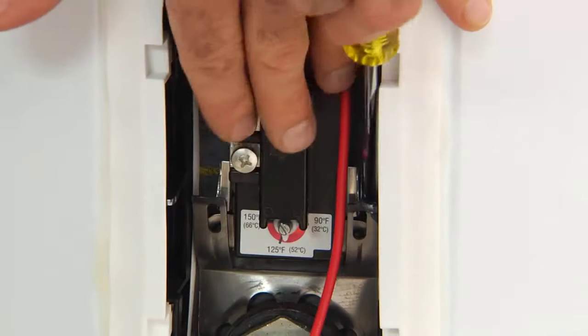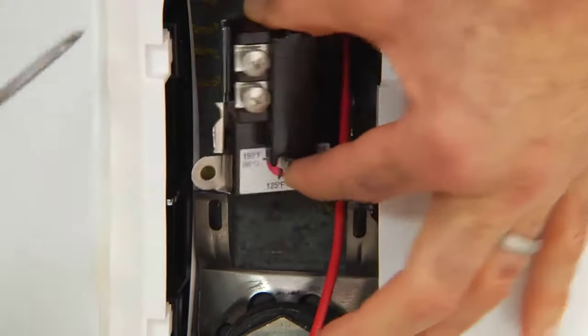Remove the thermostat by lifting it out of the retaining bracket. Be careful not to pull too hard. Breaking the retaining bracket will require the entire water heater to be replaced.